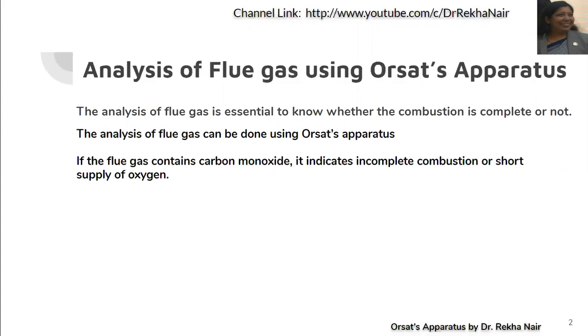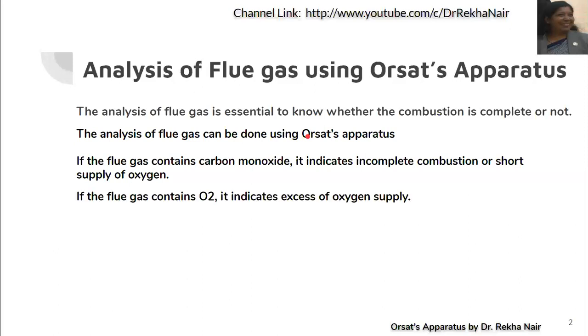If the combustion is not complete, then carbon will react with oxygen to form carbon monoxide, not carbon dioxide. It means that if carbon monoxide is present in the flue gas, it indicates incomplete combustion or a short supply of oxygen. If the flue gas contains excess oxygen, it means that excess oxygen supply was given during the combustion process. A large amount of carbon dioxide indicates complete combustion of the fuel.